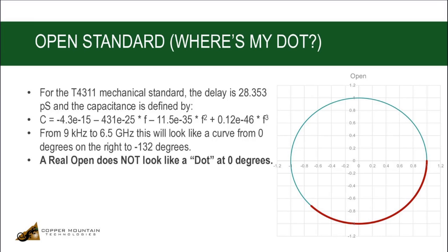So where's my dot? I have people ask this. For this particular cal piece, the delay is 28.353 picoseconds from the connector to the actual open. And the capacitance at the end of that delay is defined by these coefficients. It's minus 4.3 times 10 to the minus 15, minus 431 times 10 to the minus 25, and so on, times F and F squared and F cubed.